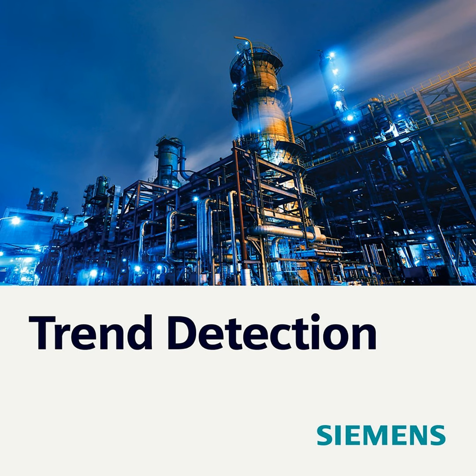I think as long as you have a background in rotating equipment, and a desire to learn and solve problems, you can really get started. There are a lot of online resources. Siemens can help in that regard. If you're looking to start a predictive maintenance program or a vibration analysis program within your facility, you can learn on the job. That's going to be important. And then there are training organizations like Mobius Institute and Vibration Institute that can help get you certified, so that you can be assured you have a certain amount of knowledge to take forth. It goes through 4 tiers of certification. The first tier starts with being competent on installing sensors and selecting the right sensors, as we discussed today, because that really is the critical start.